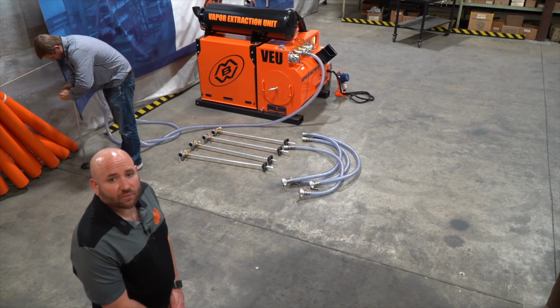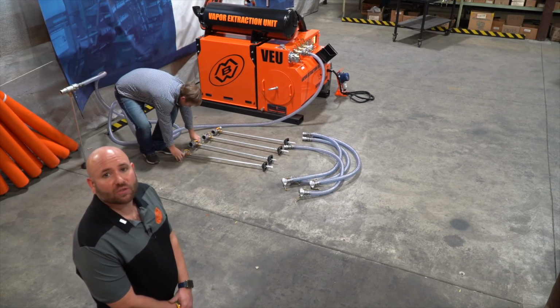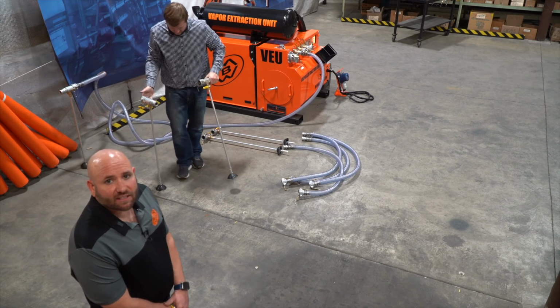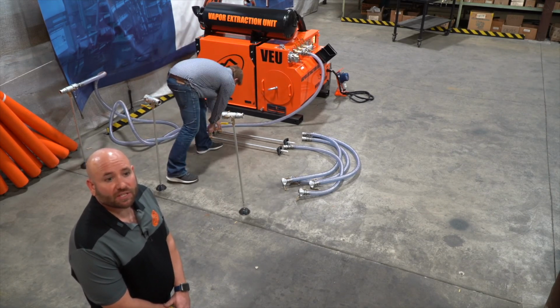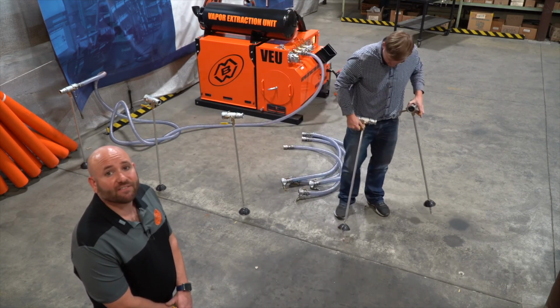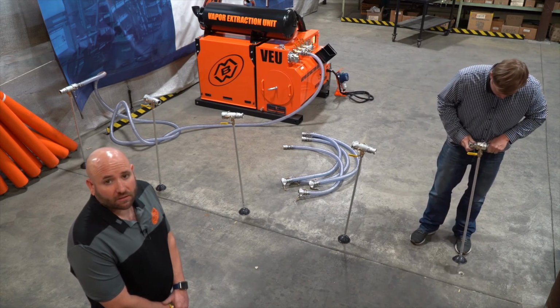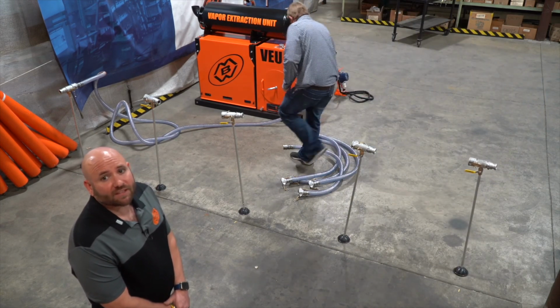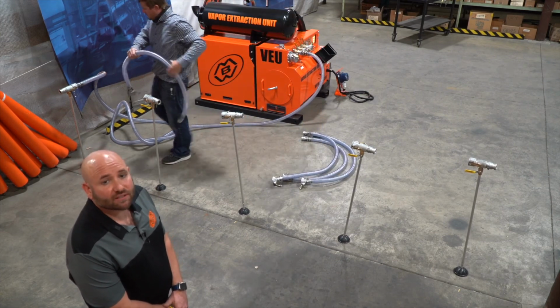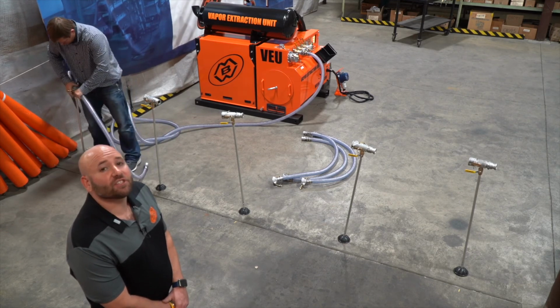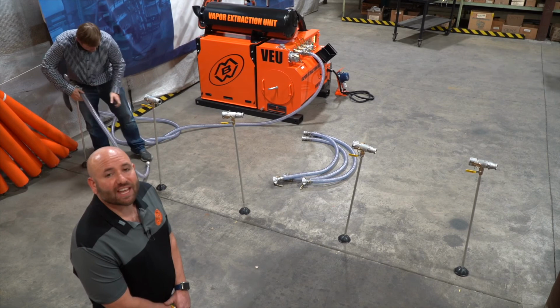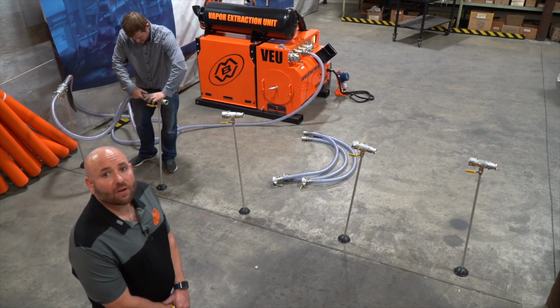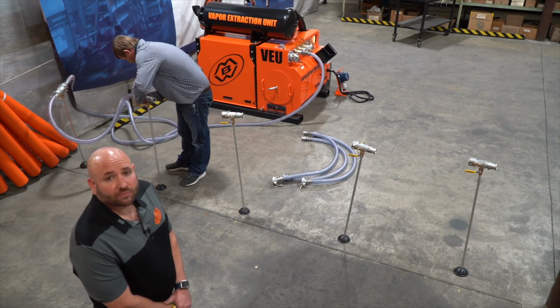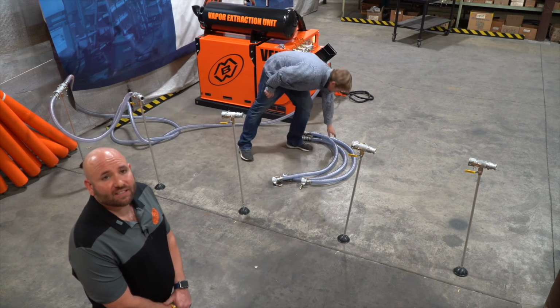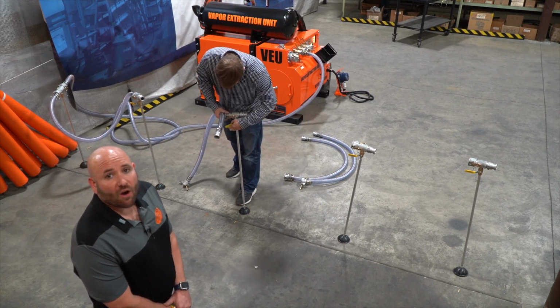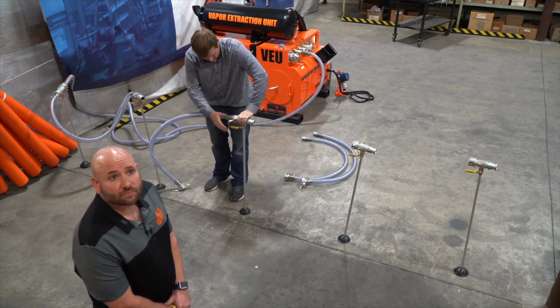In the meantime, I like to discuss the length of hose to your first probe. We have tested and seen production of the VEU not dropping off from up to 125 feet of hose away from the unit. The other thing I want to mention is that we have modified our VEU probes over the years, and we've increased the efficiency of the VEU probe by 70% by just widening that top valve. Also, my associate is making sure as he's setting up that the VEU probes are all turned off.